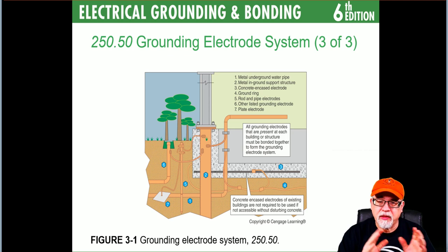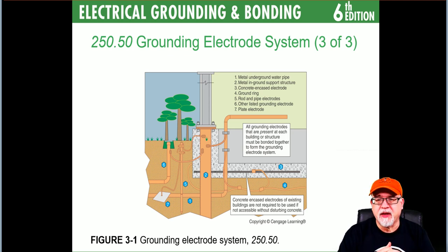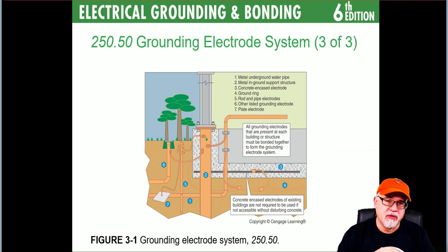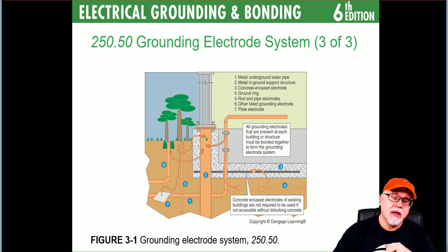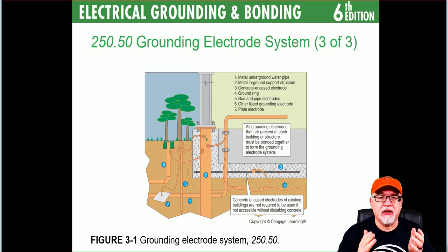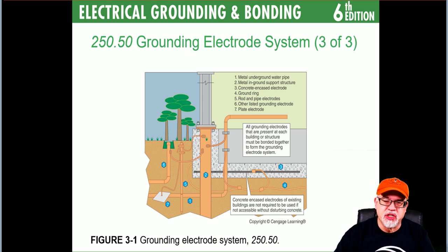All of these electrode types have to be tied together. Commonly, if you had a water pipe ground, the five-foot point of entry is where you can interconnect all the different electrodes. You cannot use rebar under the 2020 National Electrical Code as an interconnection point for other electrodes — that was made very clear in the 2020 edition.